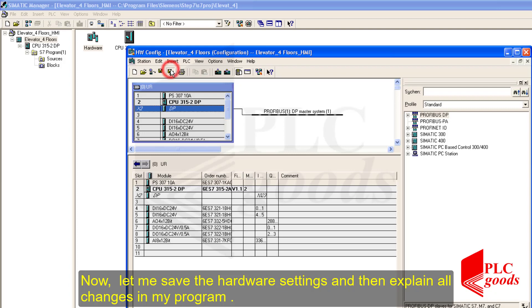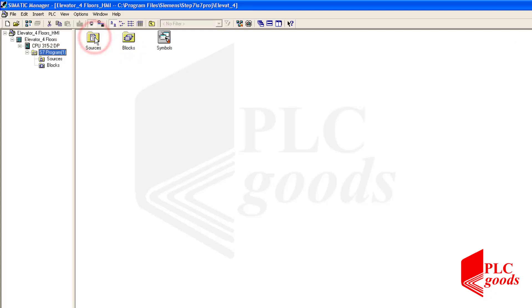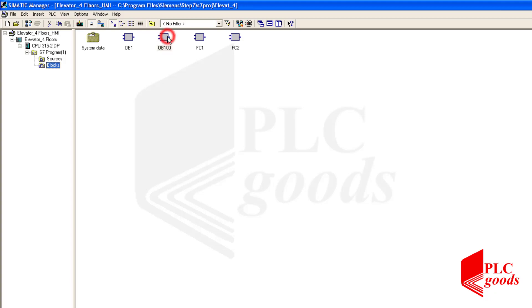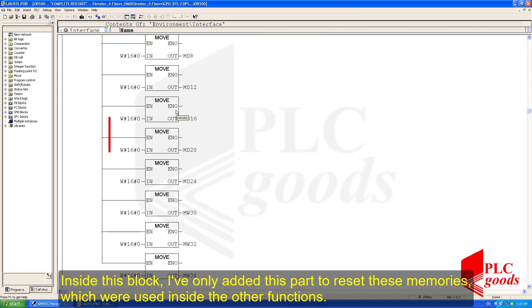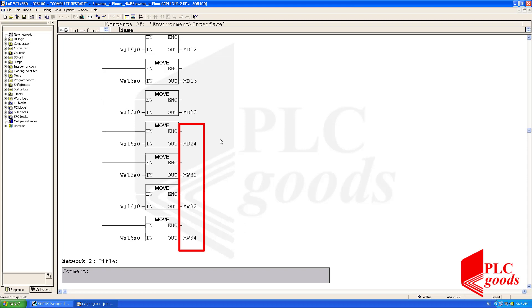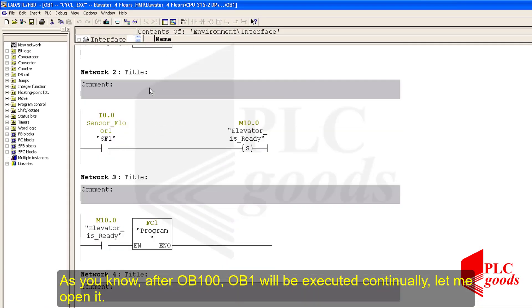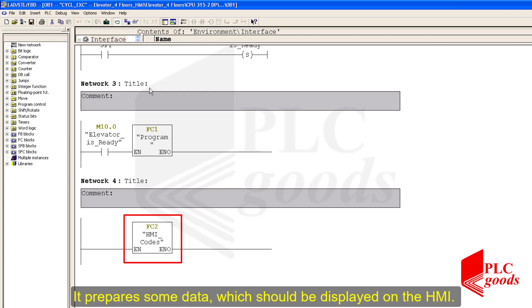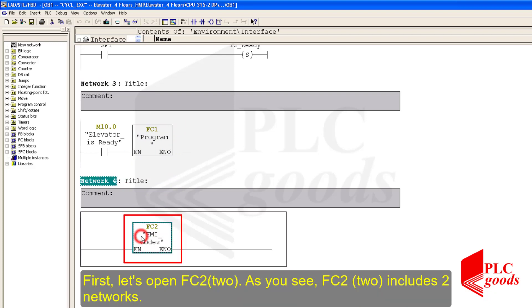Now let me save the hardware settings and then explain all changes in my program codes. As you know, PLC starts its work from OB100. Inside this block I've only added a part to reset the memories which were used inside the other functions. After OB100, OB1 will be executed continuously. As you see, a new function FC2 has been added to my previous program — it prepares some data which should be displayed on the HMI. Also, I've changed the first network FC1 a little. First, let's open FC2.